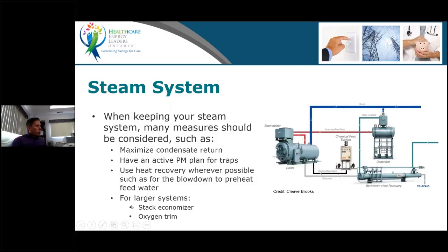We talked about the stack economizer. No, we did not. With oxygen trim, I talked about that. That's what will make sure you have the right amount of air for proper combustion of your gas. But that will usually be in a fairly large plant. Hospitals could have those. Long-term care is unlikely to have this because the boilers are too small.